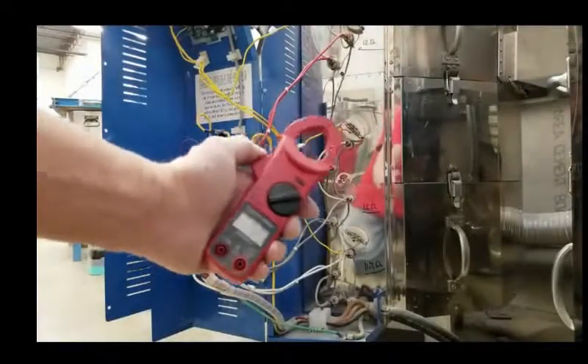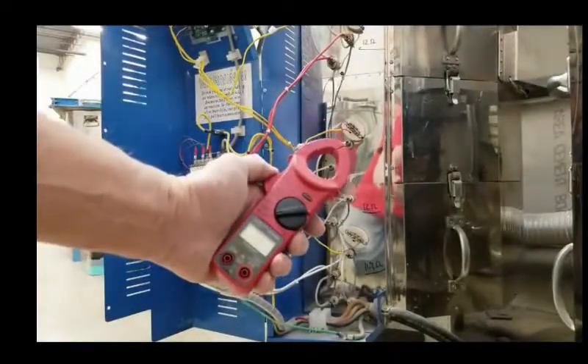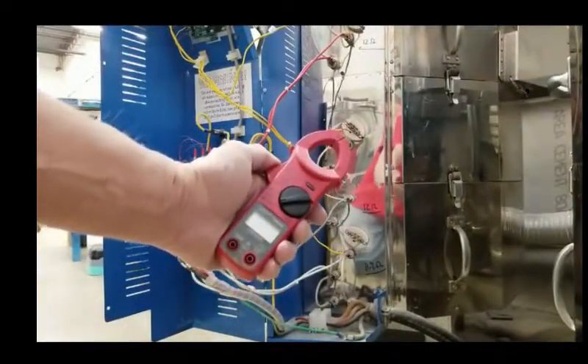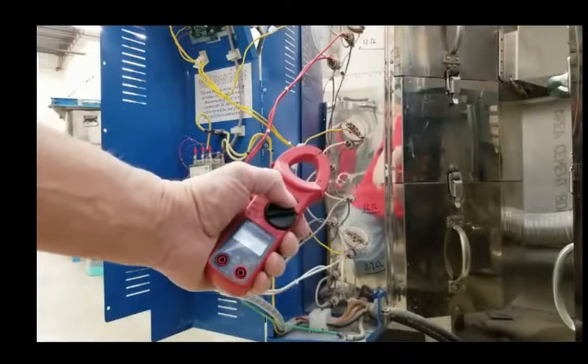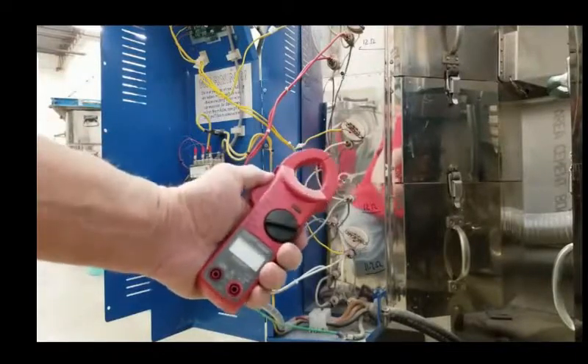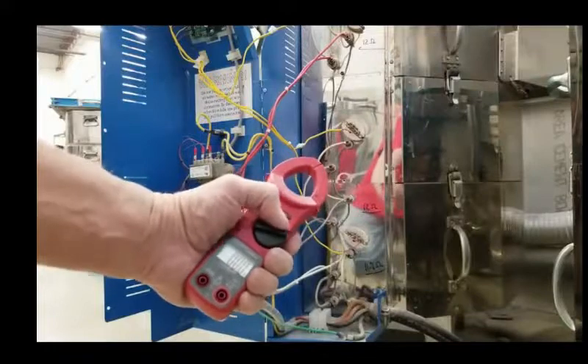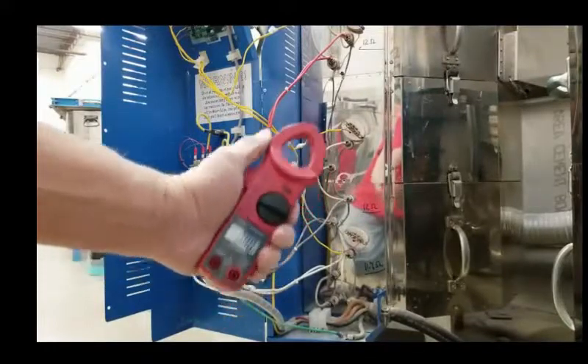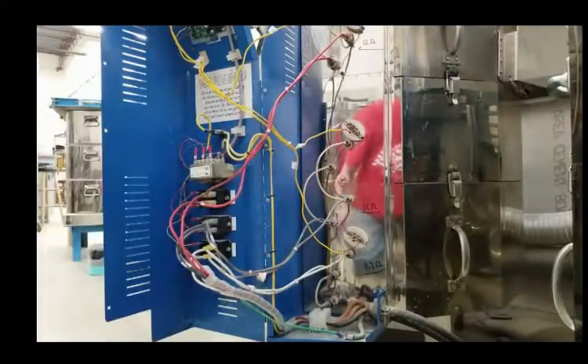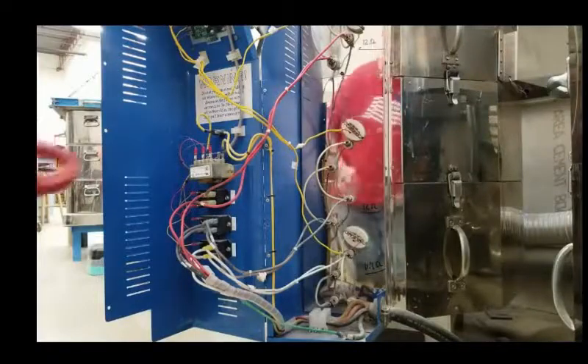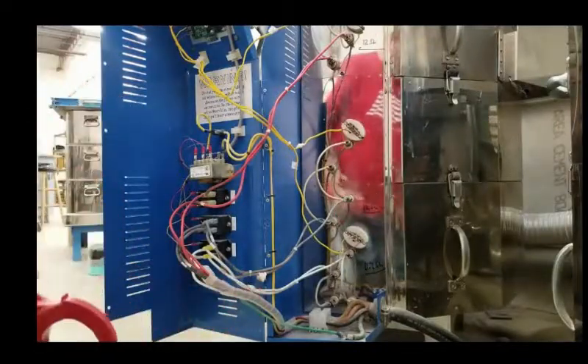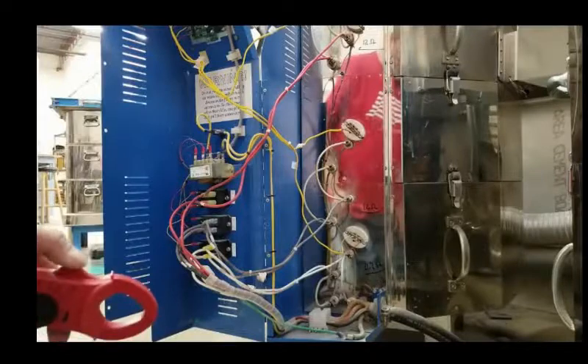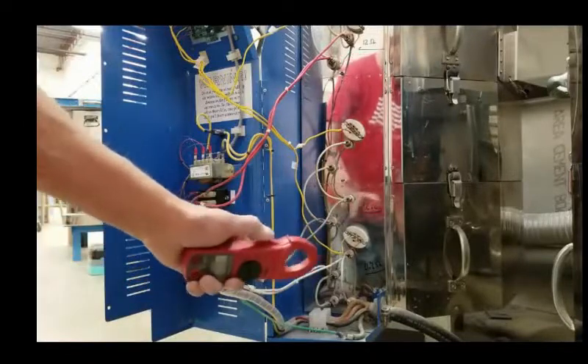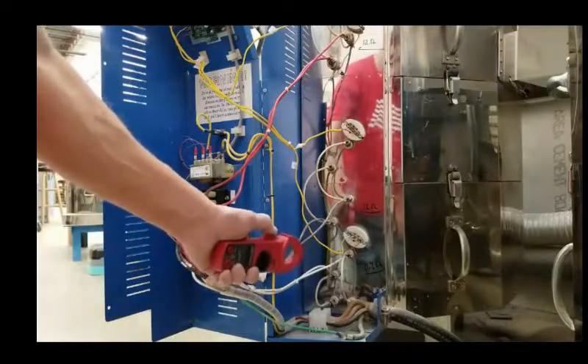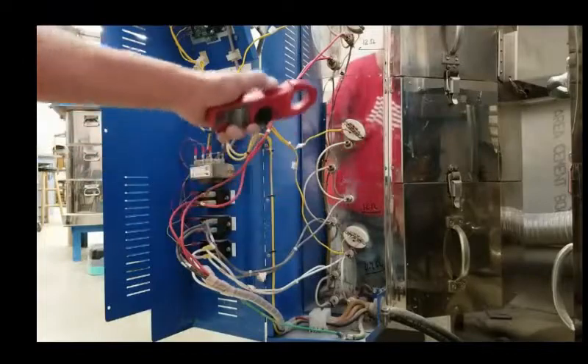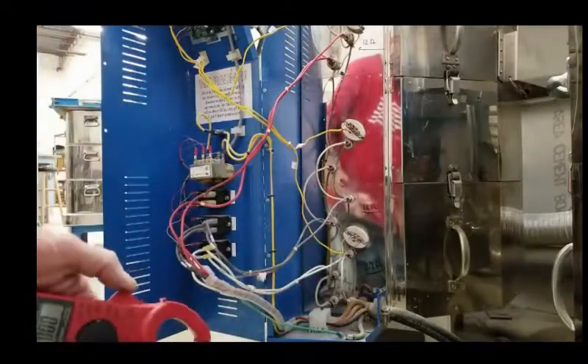Okay, we're back. We found our clamp-type amperage meter where we clamp it around the wires, and I'm going to set the scale. In this case, 40 amp scale is plenty, and I'm going to go ahead and check each circuit of elements—the third one, the second one, the first one, or top, middle, bottom, however you want to look at it.